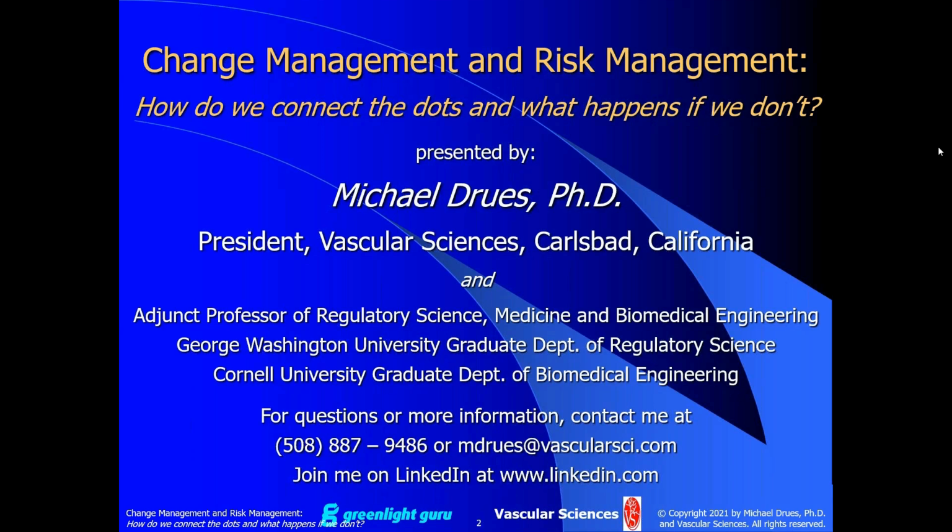So once again, if it's a cosmetic change, the outside housing of a box or something, then it's not a snowball's chance here in Southern California that change is going to impact the results of that clinical trial. On the other hand, if that change could impact the results of the clinical trial, now you run the risk of, when FDA looks at this, they say, you know what, you've made a change to your device. That change could impact safety, efficacy, performance, risk, yada, yada. That change could impact the results of the clinical trial, and therefore we want you to do that whole clinical trial over again.